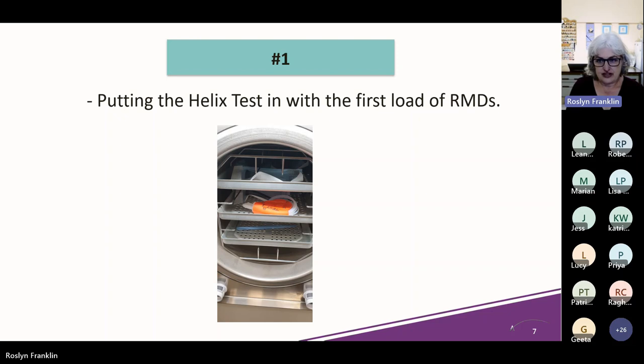Mistake number one: putting the Helix test in with that first load of reusable medical devices. Every day we need to run a couple of autoclave tests to make sure it's working properly.